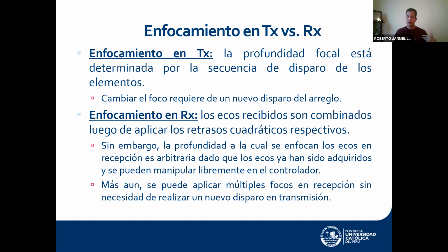So beamforming on transmission limits how fast I can create the image, because I put in the electric signals and then physics happens. On reception it is the other way around. Physics already happened. That's the part that limits the time frame I have to obtain more measurements from the ultrasonic system. After that, shifting and adding is done electronically.